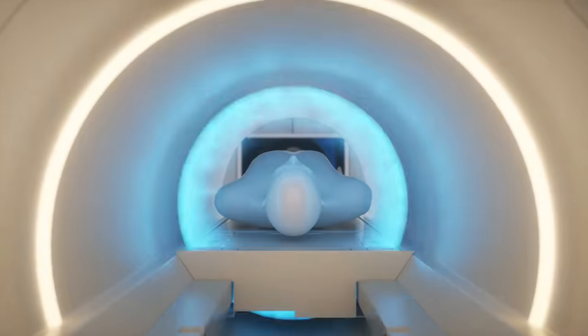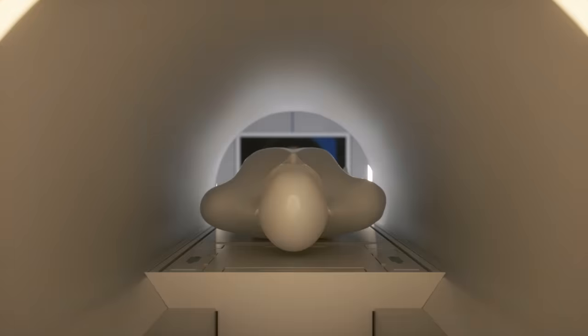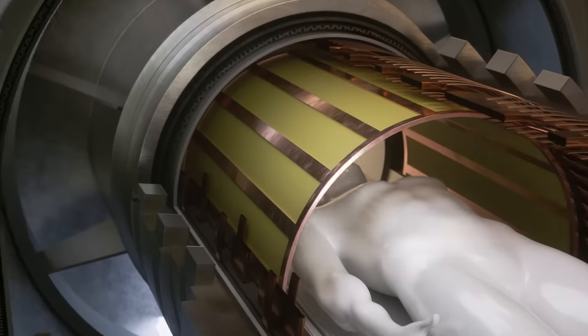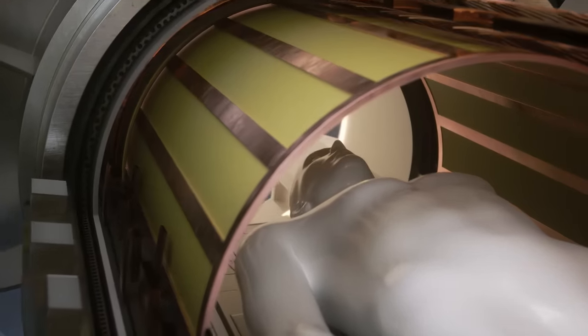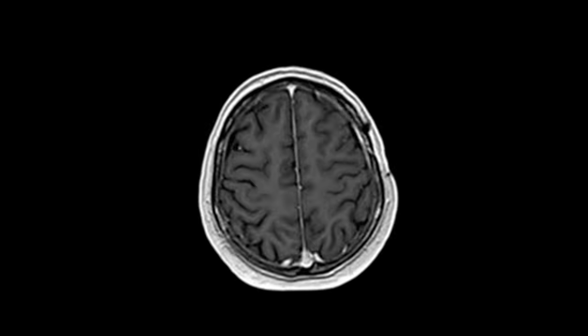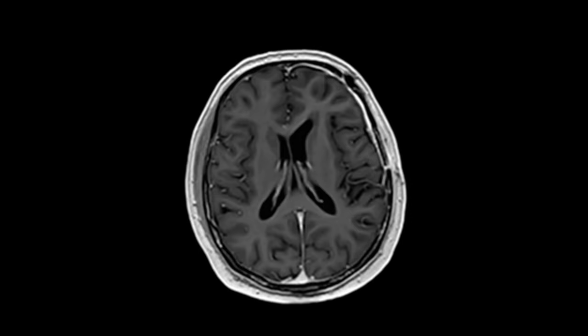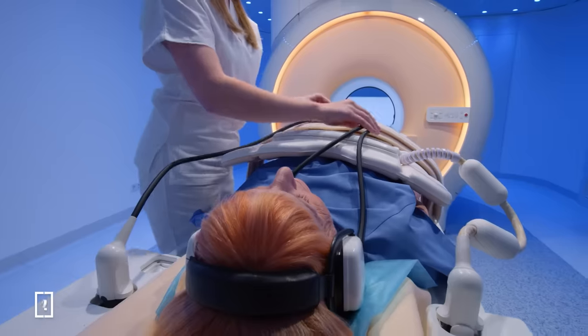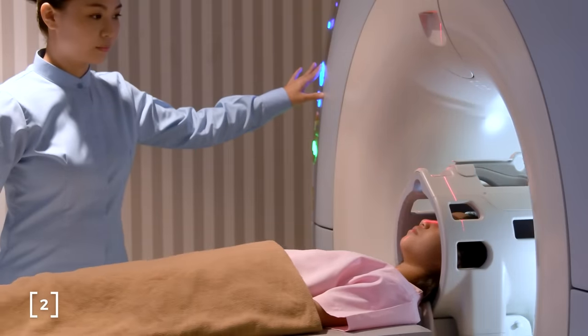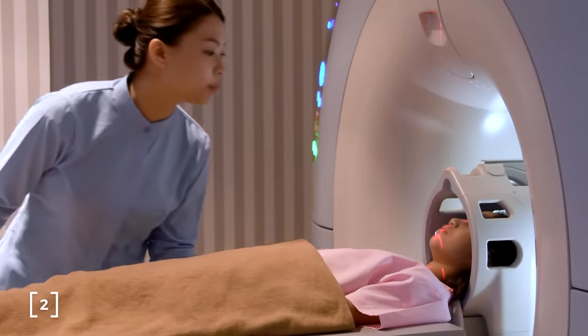MRI machines can use the same coils to send the nudge pulses and to read the signal from the body. These coils are placed as close to the patient as possible, but still inside the MRI tube. For higher contrast and resolution, some machines use separate coils to transmit pulses and to receive the signal. This allows the receiver coils to be placed much closer to the body, maximising the strength of the signal.